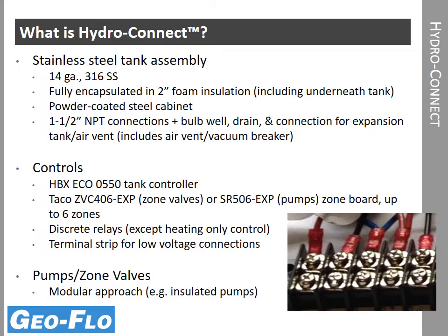Connections are 1.5-inch female pipe thread. We also have a well for the thermistor, for the bulb that senses temperature of the tank. There's a drain connection, and then at the top is the connection for the expansion tank and air vent. It does include an air vent vacuum breaker with the package, but the expansion tank and the other hydronic accessories are field supplied.